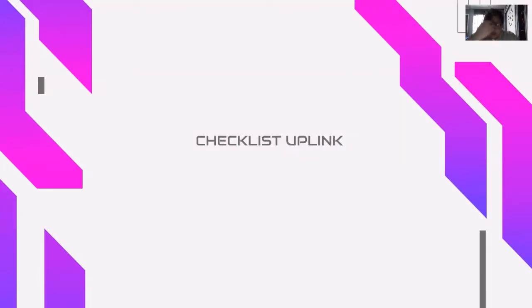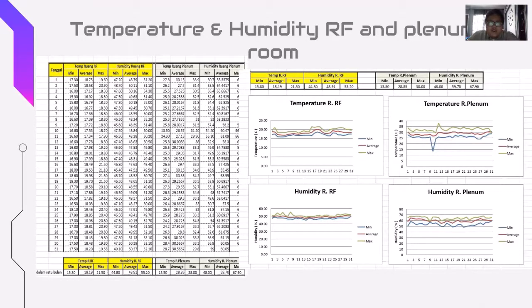For the uplink checklist, we don't actually do all of them. They said to just do these. First is the temperature and humidity in the RF and plenum rooms. The RF room is basically the shelter where we keep the KPAs, and the plenum room is the battery room, which I mentioned before. Each room has to be kept at an average temperature: around 18 degrees for the RF room, and around 30 degrees for the plenum room. That is the optimal temperature so that there won't be any condensation, so the water won't interfere with the appliances.